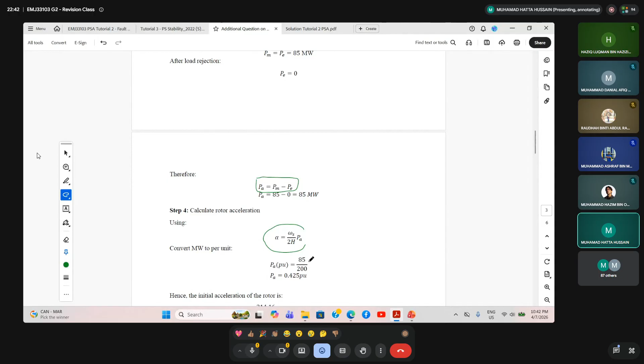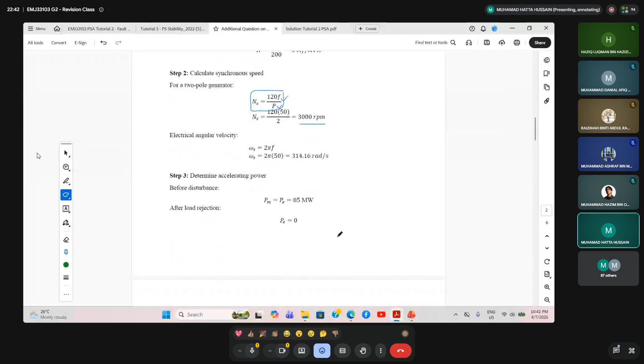Which means the actual divided by base. Because the base, we know, is equal to 200 megavolt ampere, the rating here. So this is the reason why 85 divided by 200, so I have 0.425 per unit. And then I have to calculate the initial acceleration according to this formula here. So I plug in all the values, the omega s, the synchronous speed, divided by 2 times the inertia constant given in the question, and then times 0.425 per unit.